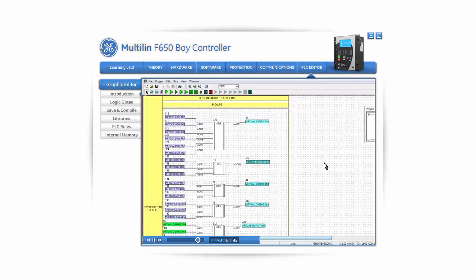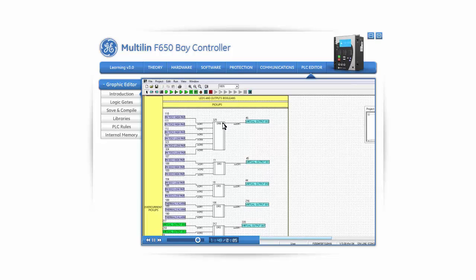Now let's take a look at the built-in logic that your relay has. First, the Pickups: the first part of the logic includes all the protection elements' pickup statuses. Second, the next part of the built-in logic contains all the protection elements' operation signals. Third, the last part is an OR gate that operates a virtual output that defines a general trip. This general trip virtual output will operate once any protection function in the relay operates. Using the built-in logic, the user can directly install and use the F650 without having to configure any additional logic.